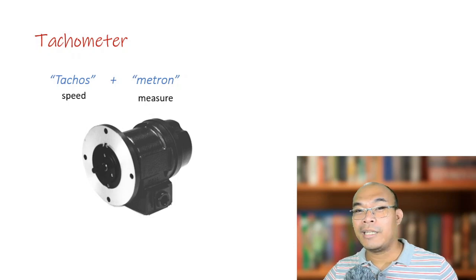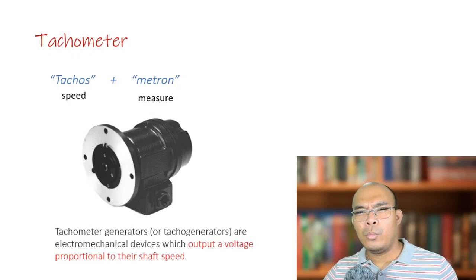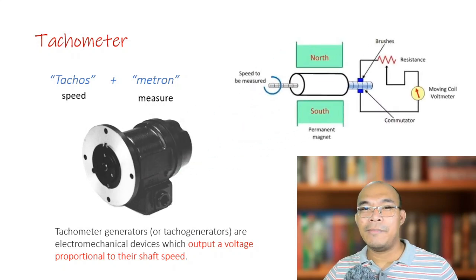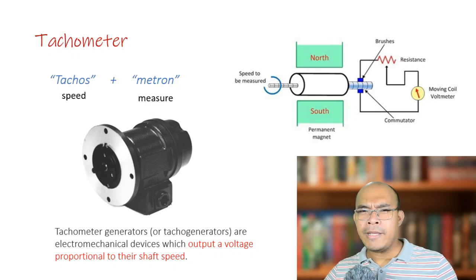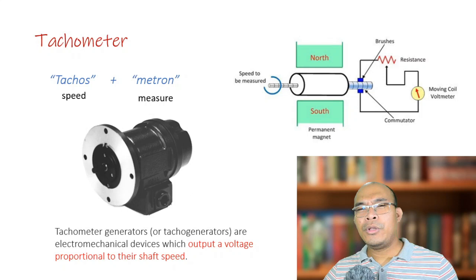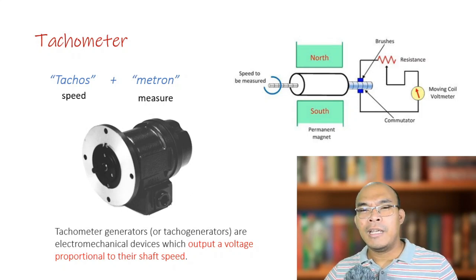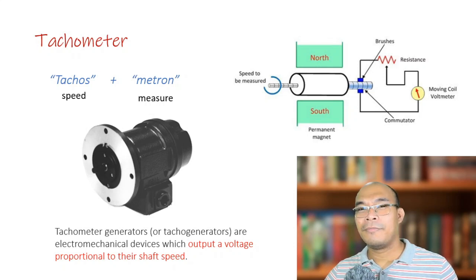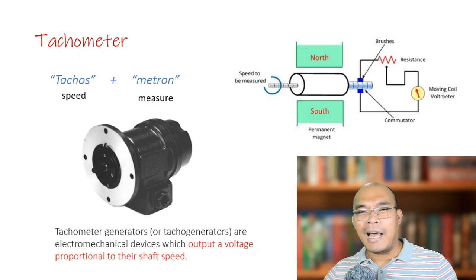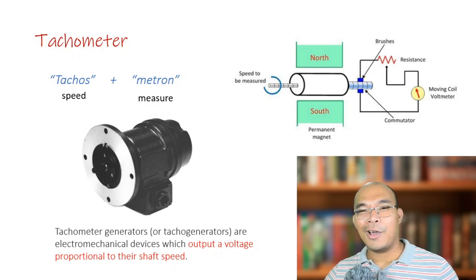This figure here is an example of a tachometer generator or tacho generator, which outputs a voltage proportional to the speed being measured. This figure here is a schematic diagram of a DC tacho generator. Based on that concept, what will happen to the output voltage if the speed of the shaft being measured increases? Since speed and output voltage are directly proportional, the higher the speed being measured, the higher the voltage generated by the tacho generator.